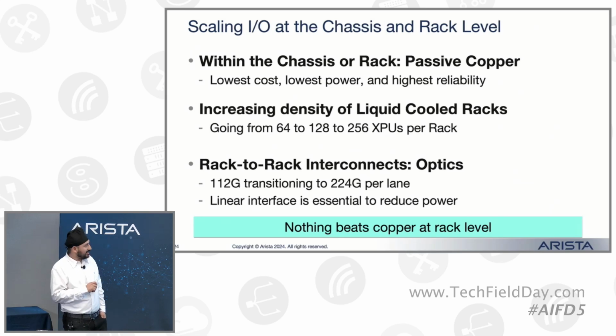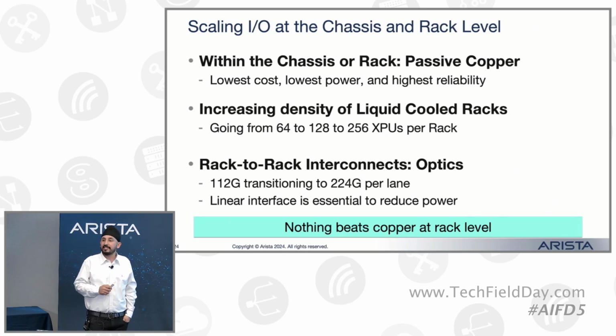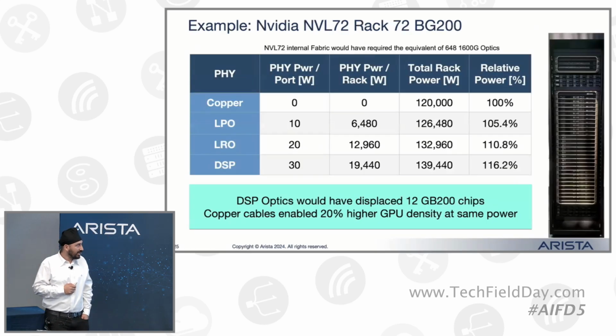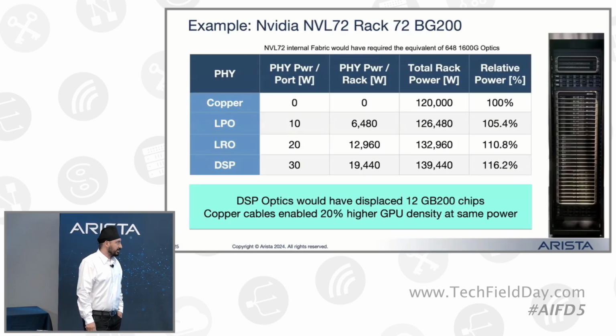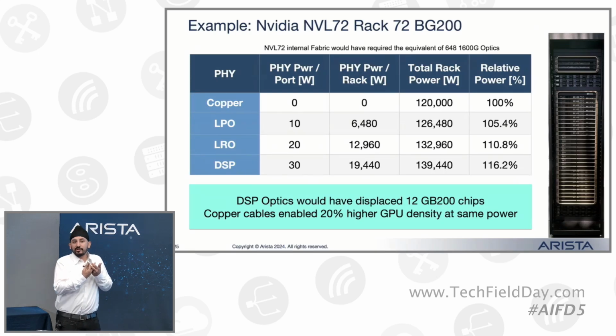From rack to rack connection, you need optics. If you have a large cluster, those optics add up pretty fast and the power adds up pretty fast. Here's an example of the NVL72 rack - there's a full mesh copper backplane, letting them get to that 120 kilowatt on the rack. If you used optics instead to connect those 72 GPUs, you'd be spending at least another 20 kilowatts just on the optics connectivity for that rack.